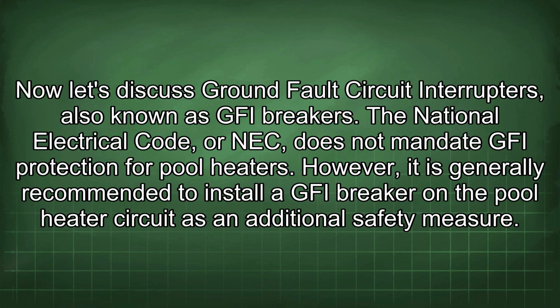Now let's discuss ground fault circuit interrupters, also known as GFI breakers. The National Electrical Code, or NEC, does not mandate GFI protection for pool heaters. However, it is generally recommended to install a GFI breaker on the pool heater circuit as an additional safety measure.